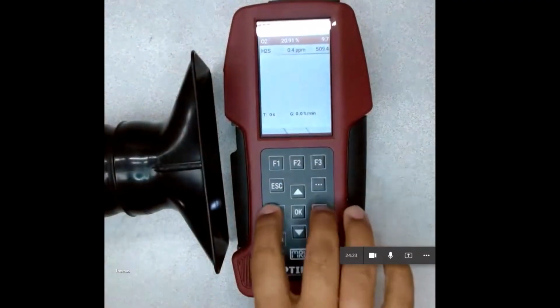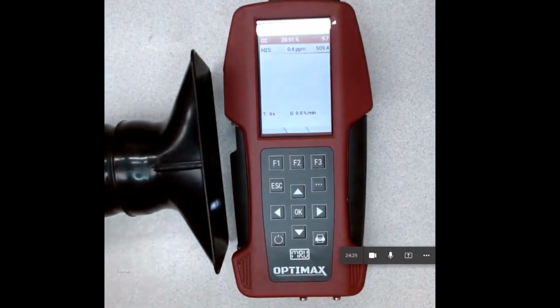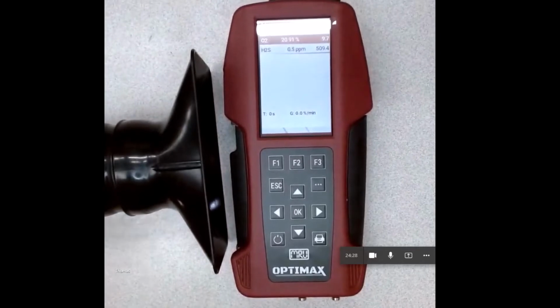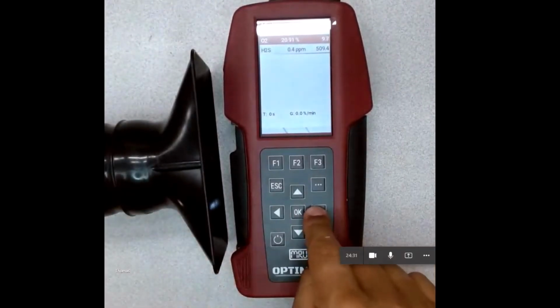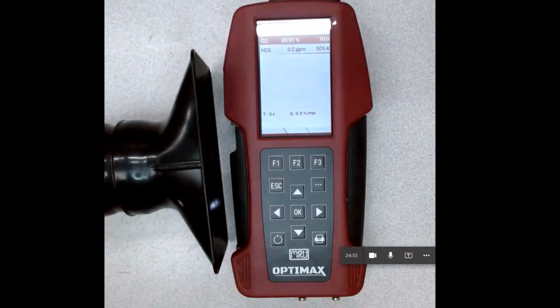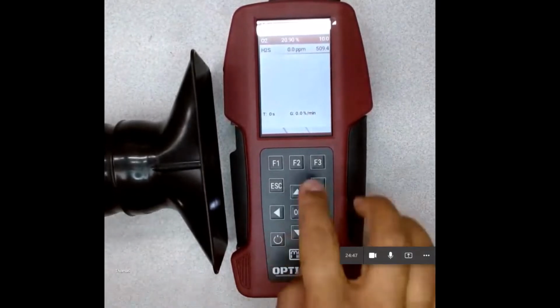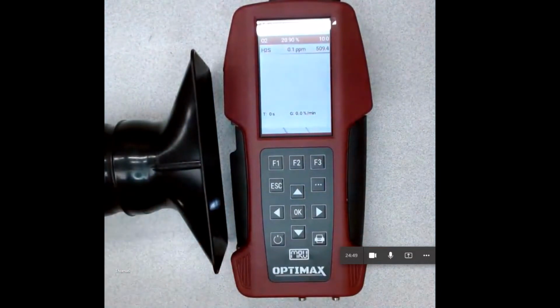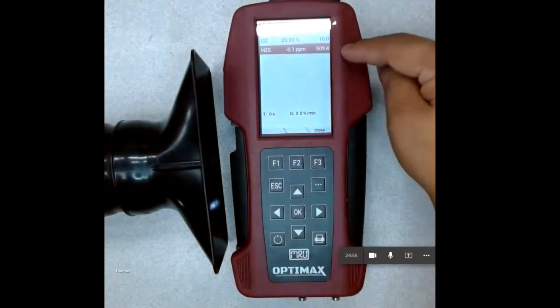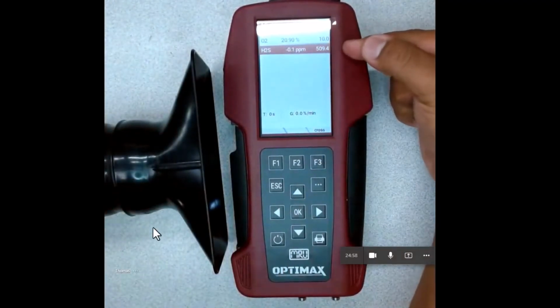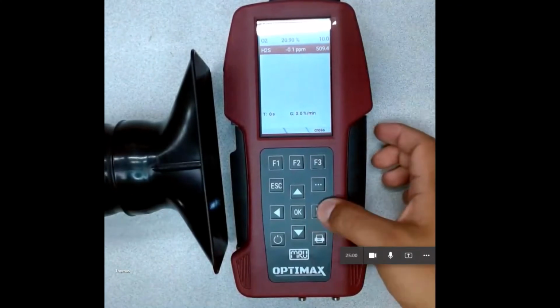So that's going to be what we set, or we should set those to our cylinder values. So for us, that would get set to 10% because our cylinder value is 9.99. Or sorry, our cylinder value is 0. But whenever we calibrate at different points of oxygen, the oxygen you won't have to adjust because we're just going to be calibrating to 0% oxygen, what you guys have in the blend. But the H2S will adjust to whatever value we have in our cylinder.